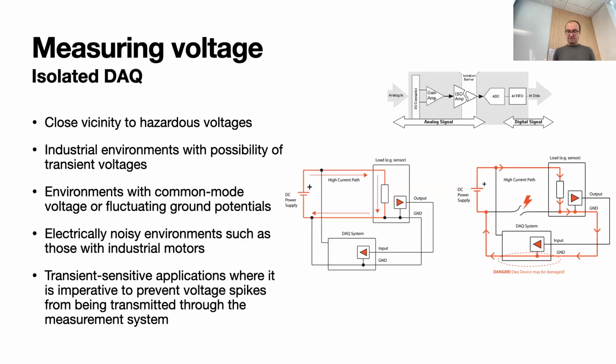So there is a chance that there is a breach due to some fault in the data acquisition, and this huge potential can go through the data acquisition system all the way down to our PC and the equipment. It would be as if somebody connects the fuel cell stack directly to some internal point in the PC, and everything will just blow out and even make a fire.